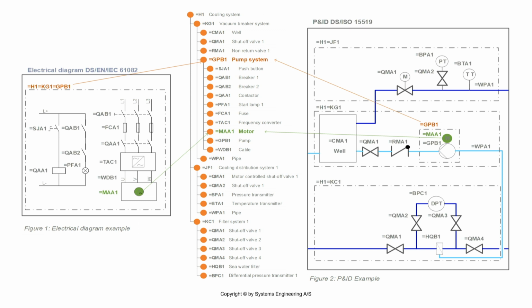So the trick, of course, is that you create the reference designation system in the middle first, and based on that one, you give the name to the motor in your electrical diagram and to the electrical motor in the P&ID diagram, or to the P&ID diagram first and vice versa. It doesn't really make any change what you want to do. But I think the new thing here is that the numbers are born in the reference designation system and given to the diagrams and not vice versa.